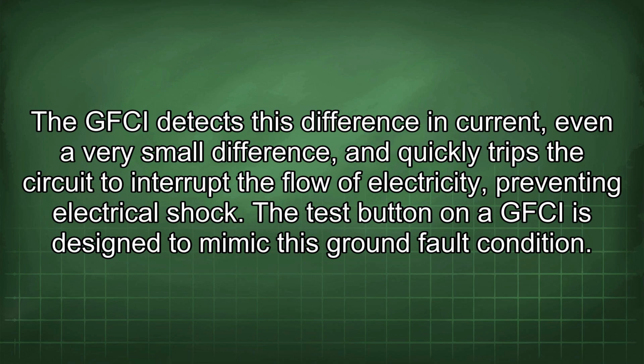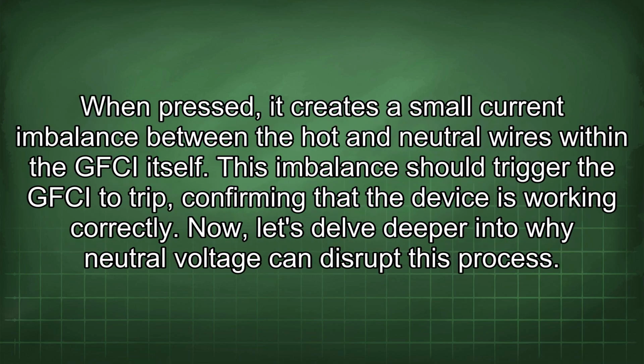The test button on a GFCI is designed to mimic this ground fault condition. When pressed, it creates a small current imbalance between the hot and neutral wires within the GFCI itself. This imbalance should trigger the GFCI to trip, confirming that the device is working correctly. Now let's delve deeper into why neutral voltage can disrupt this process.